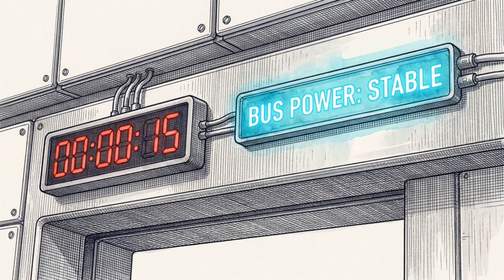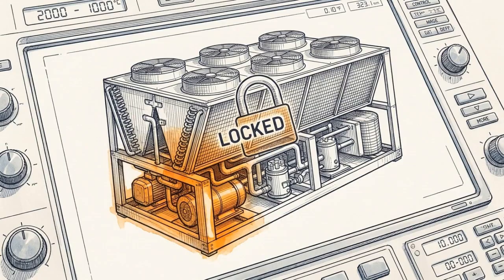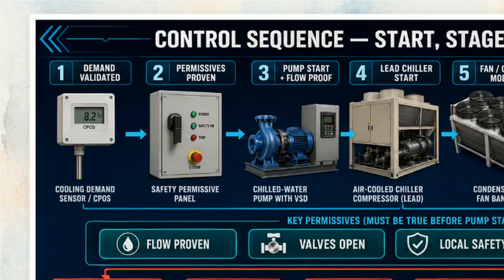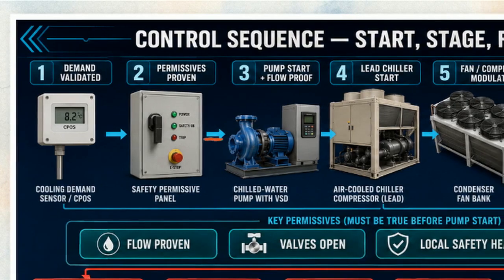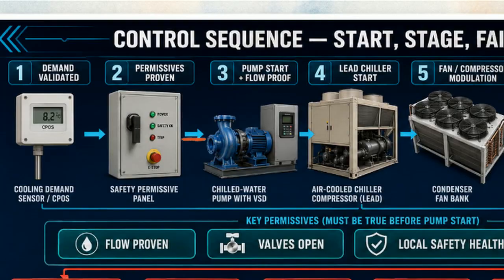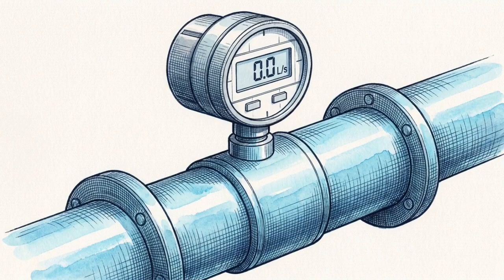At 15 seconds, the electrical power is stable, but the compressors remain locked out by the plant's control system. This control sequence diagram lays out the mandatory safety checks. Local permissives require proof of power, healthy safety parameters, and correct valve positions. Once met, the logic triggers the hydronic circuit, sending the command to start the chilled water pumps and secure a definitive proof of flow. Evaporator flow must be proven before a single compressor is allowed to fire.